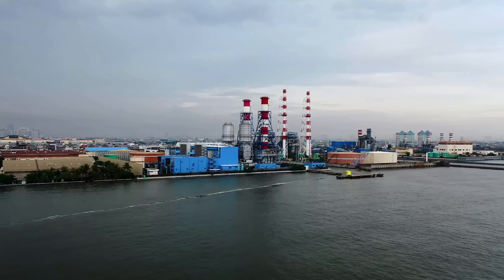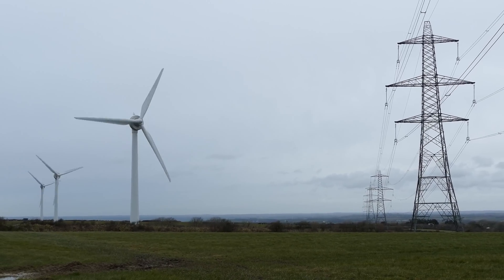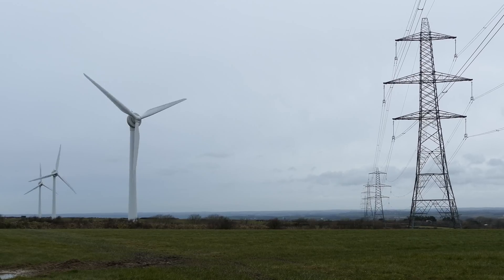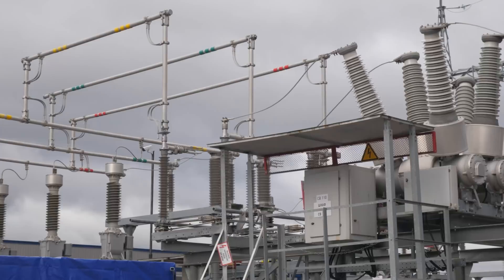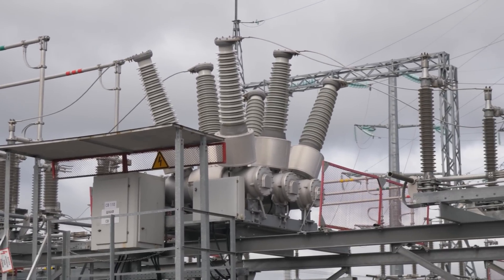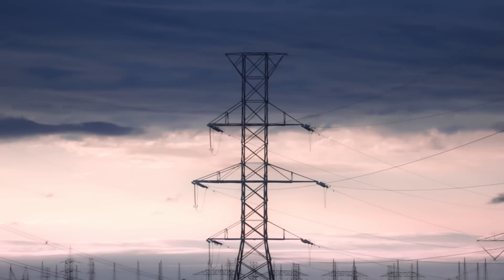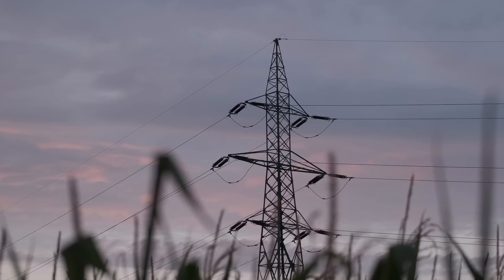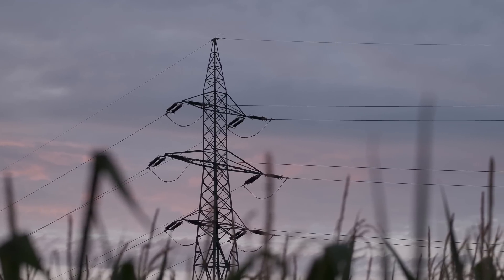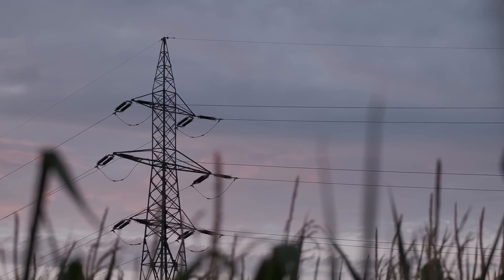One problem they face is transmission losses. Transmitting electricity from say Dungeness in the southeast to the Midlands results in huge losses from inefficiency. So they choose very high voltage, around 400,000 volts — the higher the voltage, the lower proportionately are the losses. But switching up or down the voltage causes losses in itself, plus the power lines themselves lose energy to heat. A staggering 25 terawatt hours of electricity a year is lost out of a total of 325 terawatt hours produced — about 9%. That is why the grid generally transmits electricity long distances at either 275 or 400,000 volts.